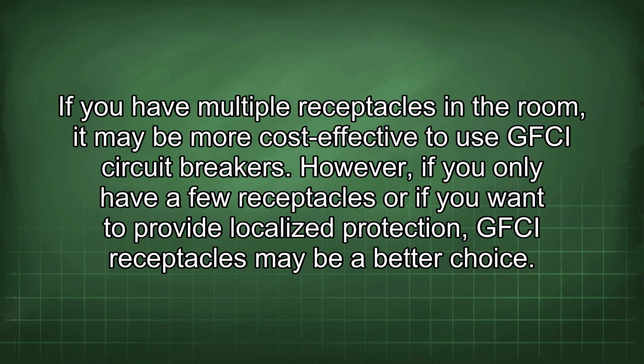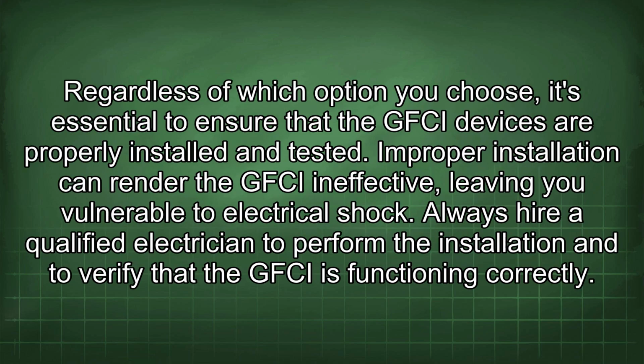If you have multiple receptacles in the room, it may be more cost-effective to use GFCI circuit breakers. However, if you only have a few receptacles or if you want to provide localized protection, GFCI receptacles may be a better choice. Regardless of which option you choose, it's essential to ensure that the GFCI devices are properly installed and tested. An improper installation can render the GFCI ineffective, leaving you vulnerable to electrical shock. Always hire a qualified electrician to perform the installation and to verify that the GFCI is functioning correctly.